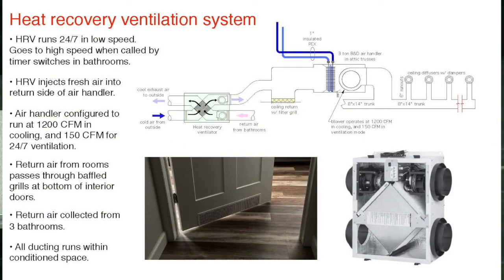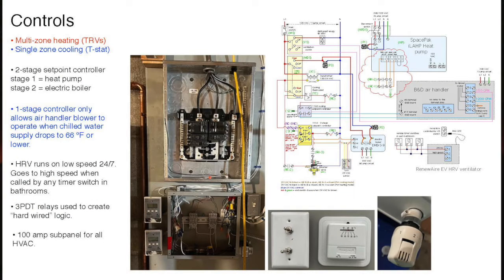The thing I liked about this, we didn't have to do return air ducting to every room. We just let it all come out into the central hallway, and then it all goes up through a filter grill. And instead of just cutting a hole in the wall that obviously light and sound would come through, we put them on the bottom of the doors. You just take a saber saw out an area, and they slip right up onto the door, and a couple screws at the bottom hold them in place. So that's how the return air was handled.